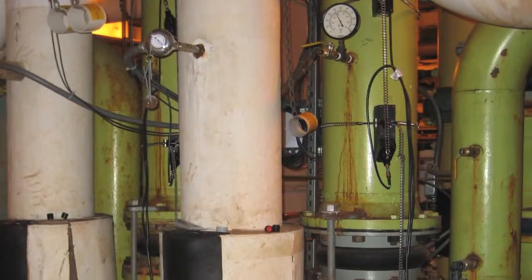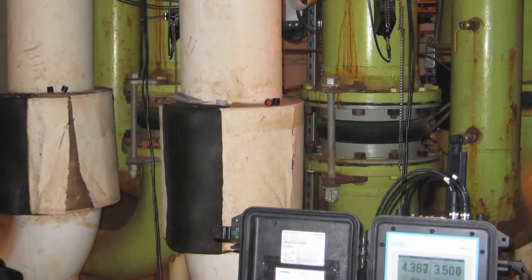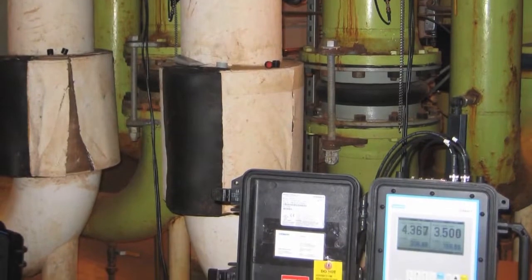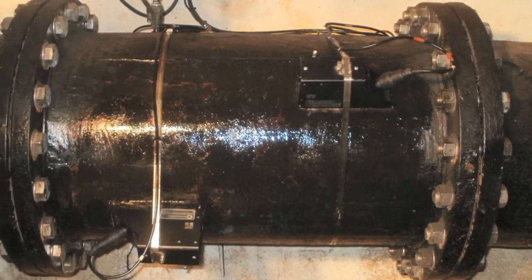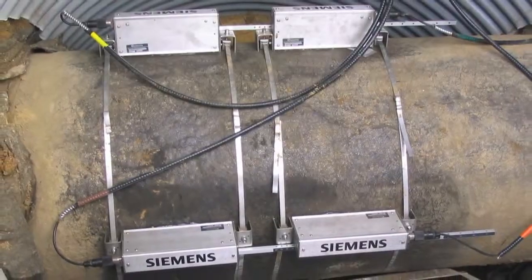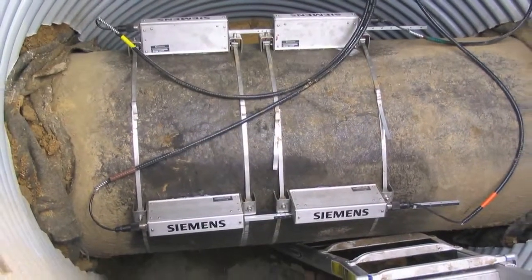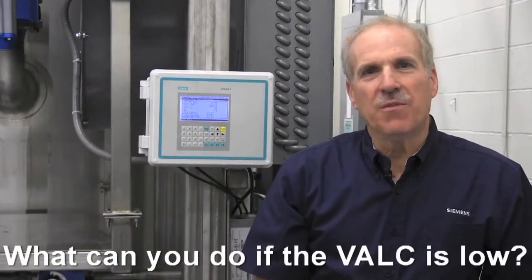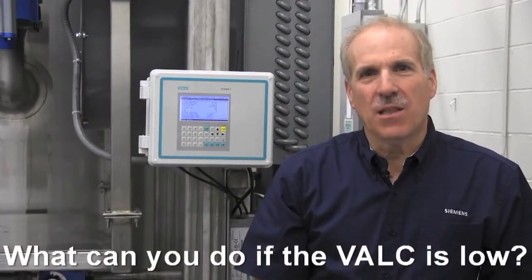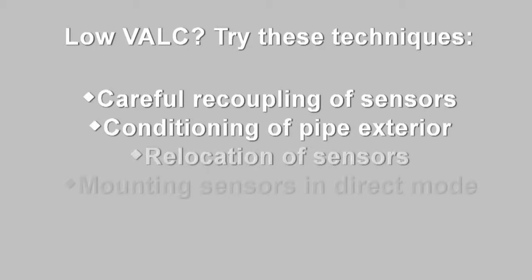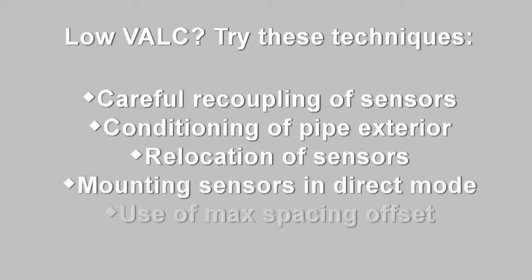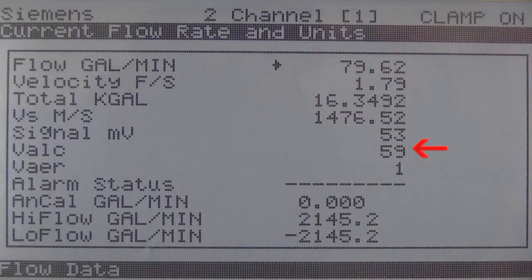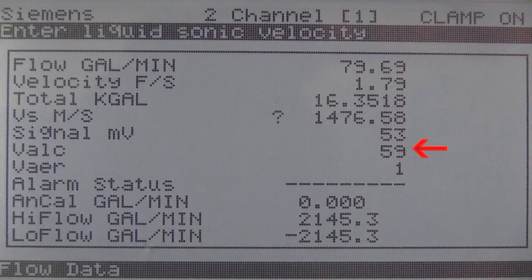Consider the condition of the pipe and viscosity of the liquid when evaluating VALC. For example, on older or poor conditioned pipes or high viscosity liquids, it is likely the value will be lower. What can you do if the VALC is low? If the VALC is low, it can usually be improved through one or more of the following techniques: careful recoupling of the sensors, conditioning of the pipe exterior, relocation of the sensors, mounting the sensors in direct mode, or use of max spacing offset. On this installation, the VALC is 59.